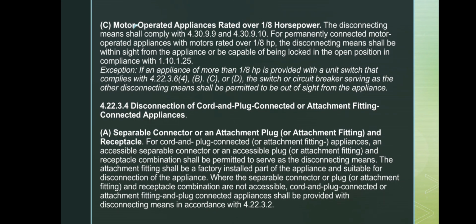Next slide, we tackle motor-operated appliances rated over 1/8 horsepower. The disconnecting means must follow the rules in 4.30.9.9 and 4.30.9.10. The disconnect must be within sight of the appliance or it must be able to be locked in the open or off position.